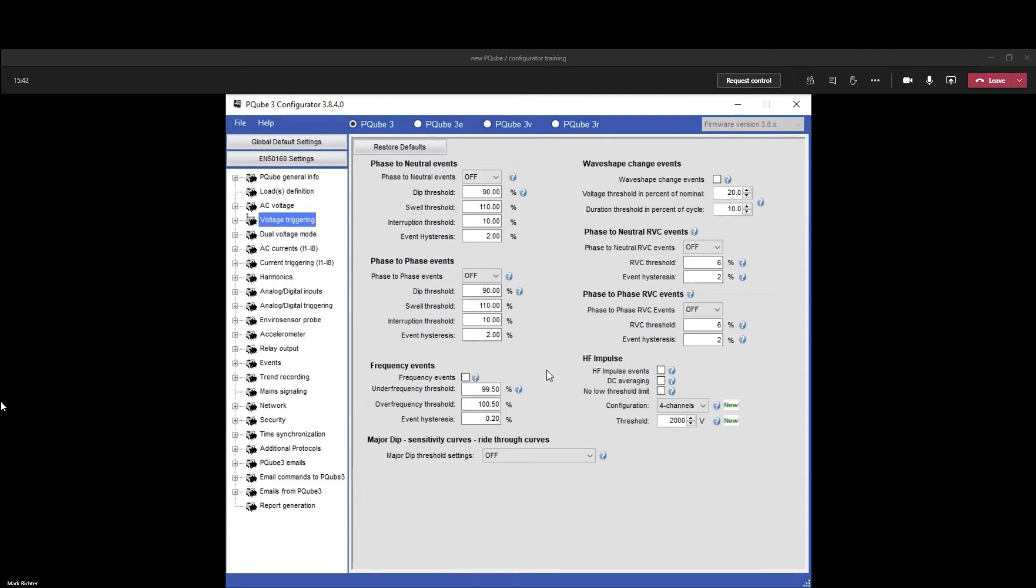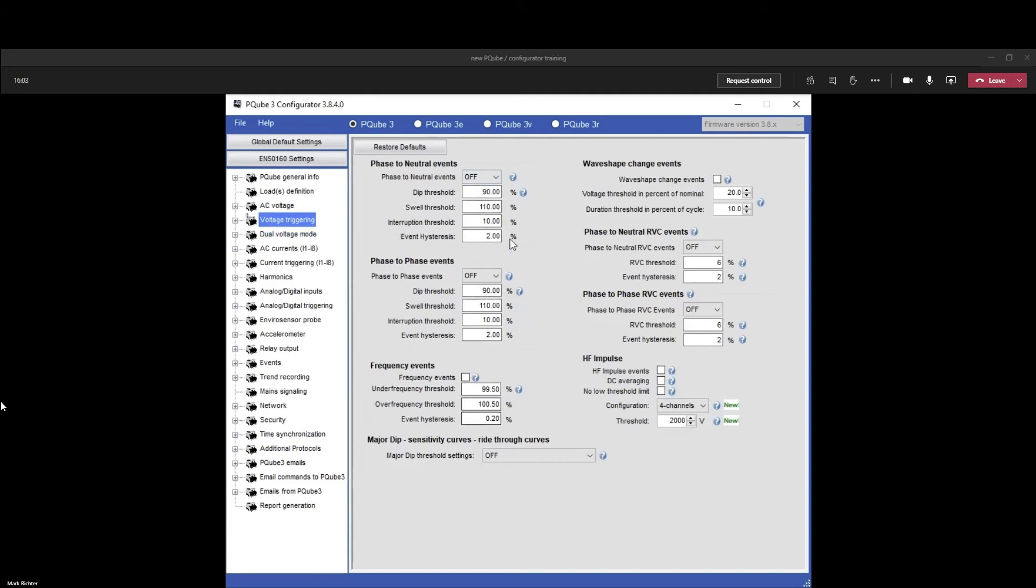You may be inundated with emails and events, and the PQube is busy writing files so it appears to act slow. My recommendation is have all the events switched off at the beginning, then record trends for a few days, then come back and set these values based upon the trend values. It's typical for a utility to guarantee you voltage at plus or minus 10 percent, and that's what these are all set up as by default.